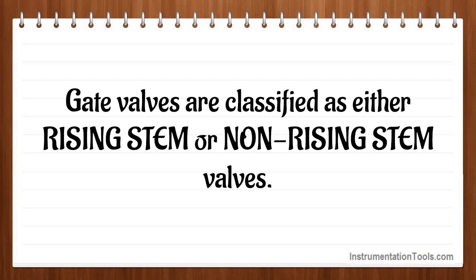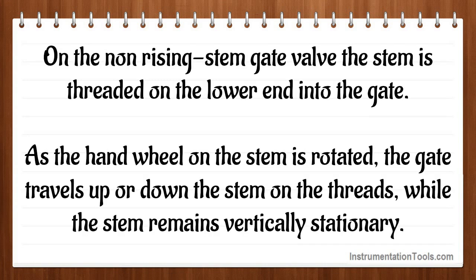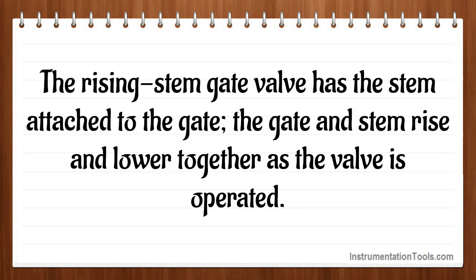Gate valves are classified as either rising stem or non-rising stem valves. On the non-rising stem gate valve, the stem is threaded on the lower end into the gate. As the handwheel on the stem is rotated, the gate travels up or down the stem on the threads, while the stem remains vertically stationary. The rising stem gate valve has the stem attached to the gate; the gate and stem rise and lower together as the valve is operated.